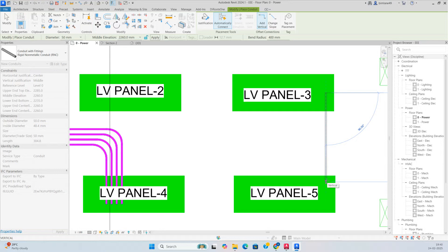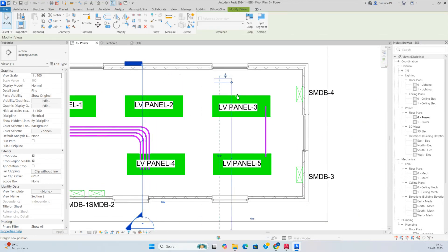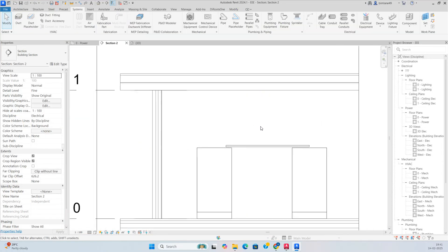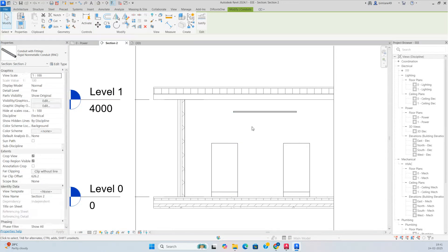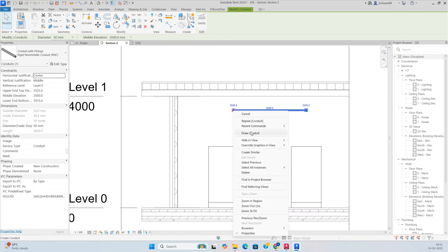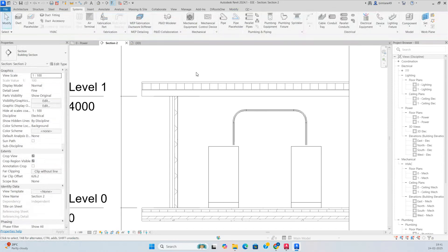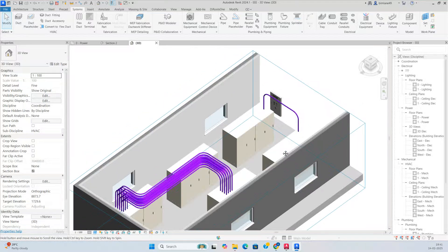You need to drop some conduits over here. Make sections from here — go to View, then give the elevation: 3500. Then draw the conduit and drop to the panel from the same location, dropping like that.